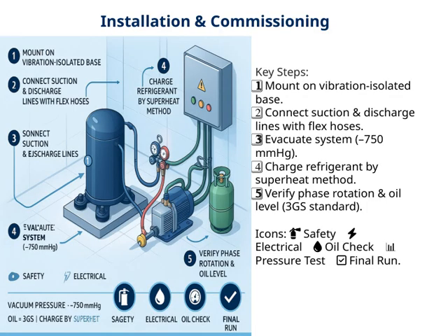Let's walk through the key steps for installation and commissioning. First, it's essential to mount the equipment on a vibration-isolated base. This helps reduce any noise and prevents issues caused by vibrations during operation. Next, we connect the suction and discharge lines using flexible hoses. This flexibility makes the connections easier and ensures a secure fit. After that, we need to evacuate the system to about minus 750 mmHg. This step removes any air and moisture, which is crucial for optimal performance and longevity of the system.